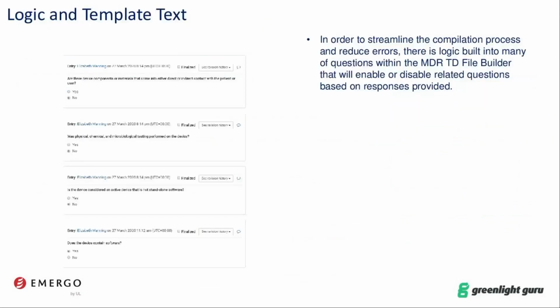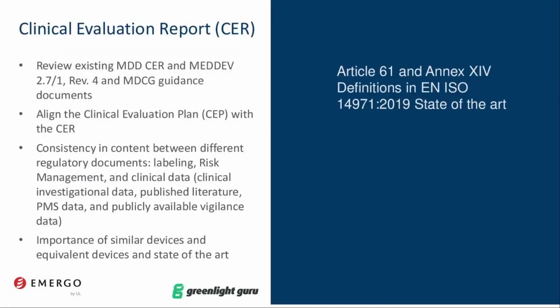And then here we'd like to emphasize the importance of a clinical evaluation report. The manufacturer should review their MDD CER and MedDev 2.7/1 revision 4. And interestingly enough, we still see MDD CERs which are not compliant to the current revision of the guidance. That's really one area where a manufacturer needs to review and ensure that their current existing MDD CER is compliant to the MedDev.